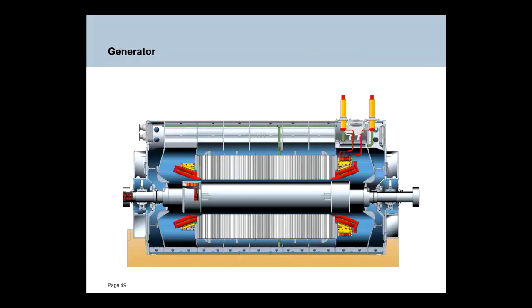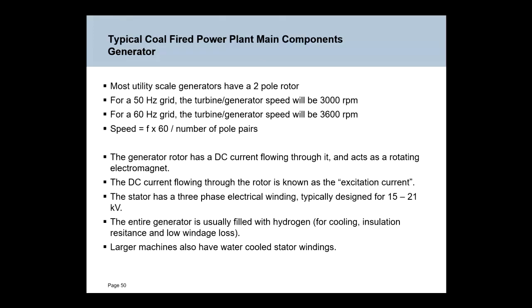So now we're going to talk about generators. So whether it's a coal-fired power station or a gas-fired power station, they all have an electrical generator connected on the end. Sort of very, very basic electrical engineering. So for a 50 hertz grid in Australia, we have 50 hertz. In the UK and Europe, there's 50 hertz. US, South America, Philippines have 60 hertz. So for a 50 hertz grid, all of the large utility machines spin at 3,000 RPM. They have 2-pole generators. For a 60 hertz grid, they spin at 3,600 RPM.